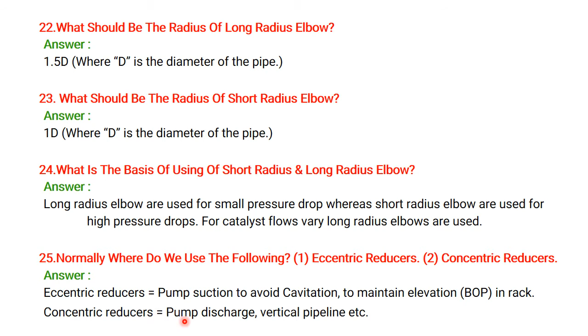Normally, where do we use the following: eccentric reducer and concentric reducer? This is a very important question. Eccentric reducer: at pump suction to avoid cavitation, and to maintain elevation, BOP, bottom of pipe, in a rack. Concentric reducer, where is it used? Pump discharge, vertical pipeline, etc. Here, is a concentric reducer used at pump suction? Yes or no?